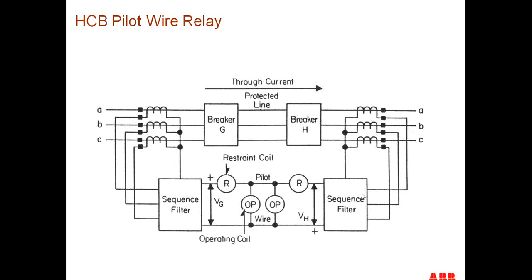And then at the remote end of the line, it used the same sort of sequence filter, so the currents would run through the sequence filter, and again it would develop a sequence voltage, VH, that was impressed on the line. So when we had a through fault current, we would get a circulation of current. The polarity of VH and the polarity of VG would be opposite each other, so we get a circulation of current on the transmission through the pilot wire, and no current through the operating coil at all.